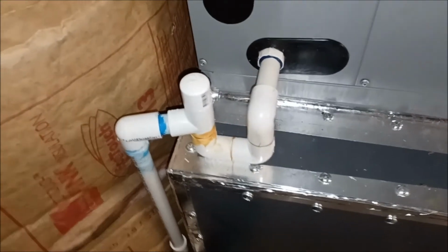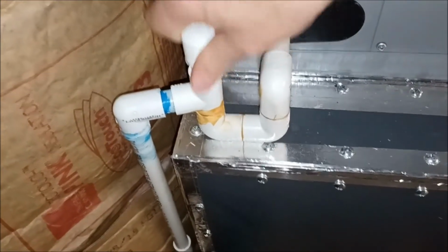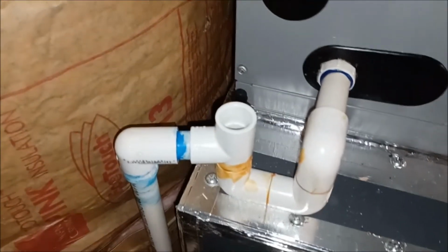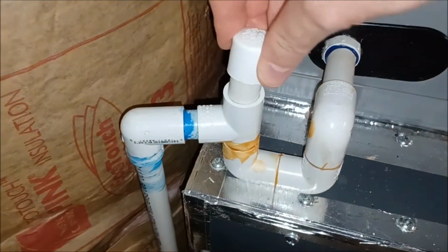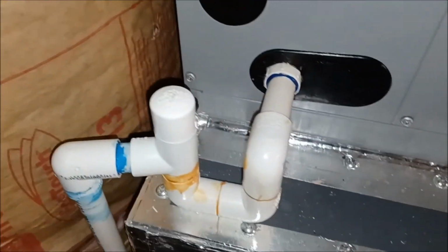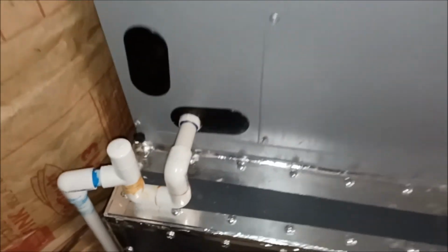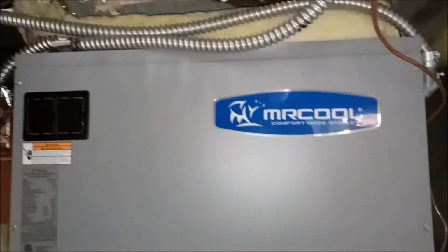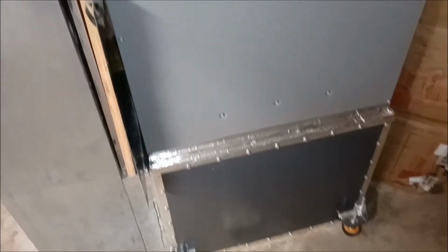So as you can see, I've got a P-trap that I installed. It's probably one of the important parts. It prevents the air handler from back sucking air into it, so it basically lets water sit in there so it doesn't suck the air back in. So that's important. And I noticed the little condensate black covers there were leaking a little bit of air, so I sealed all that up and then basically wrapped up the design, so everything's kind of done here. That's the front part. Still got some wiring to route and some insulation to put in, and that's the back, and pretty much that's it.